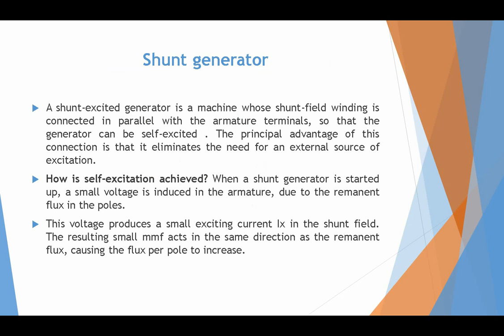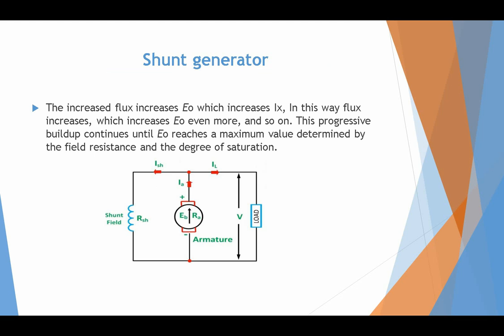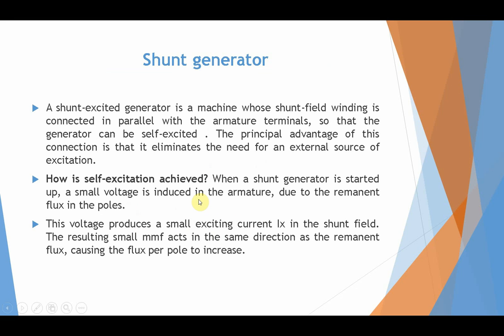Another type is the shunt generator. In a shunt excited generator, the shunt field winding is connected in parallel with the armature winding, so that the generator can be self-excited. The principal advantage of this connection is that it eliminates the need for an external source of excitation. In the separately excited case, we needed a separate source; here we do not.